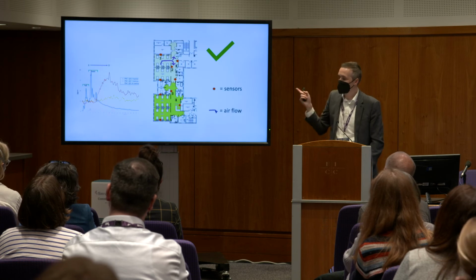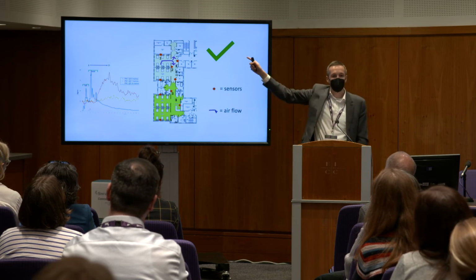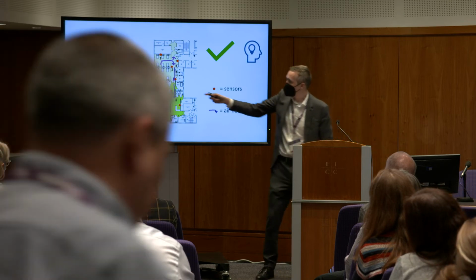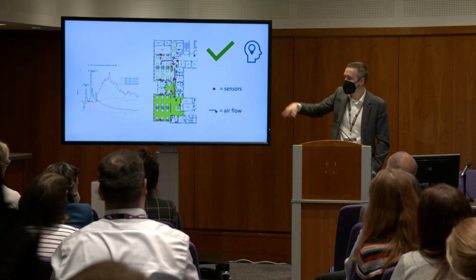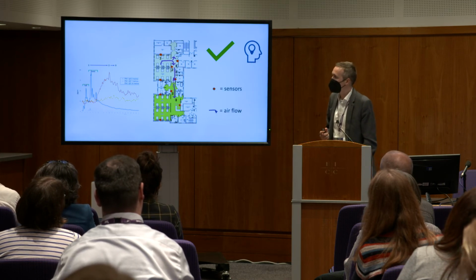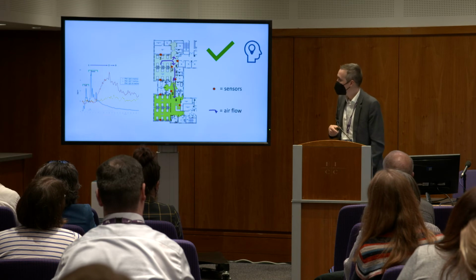But that's all good, because that's how the airflow is designed in a hospital. The air goes into the bay, and then it goes into the corridor. Good, it's away from patients. That's perfect. And then it travelled further down the ward. So that's also perfect, although it did go through the doors. Luckily, when we do open this ward as red, we start with the red ones in here. So by the time this bay is full with COVID patients, the green is already filled. So that's not going to be too much of a problem, unless you get 2 strains, I suppose.